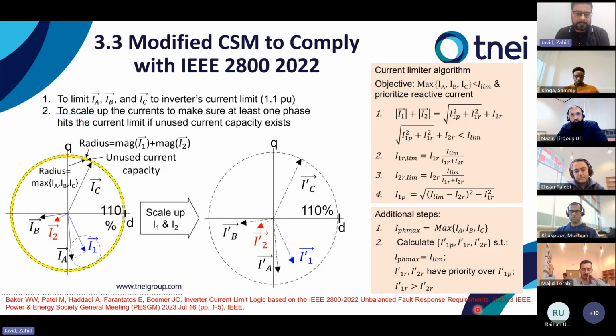So this was the paper that I was talking about. You can see the reference at the bottom of this slide. They improved the conventional current saturation method to comply with the IEEE 2800. The objective was to limit the phase current to the converter's limit of 1.1 pu, and to scale up the currents to make sure that at least one phase hits the limit if unused capacity exists. In the figure on the left side, you can see the unused capacity highlighted in yellow, and then they scale up the current in the sequence domain, I1 and I2. They are equally scaled up, and you can see in the figure on the right-hand side that it hits the limit of 1.1 pu, and the full capacity of the converter is used.